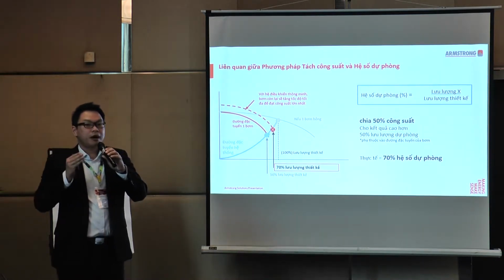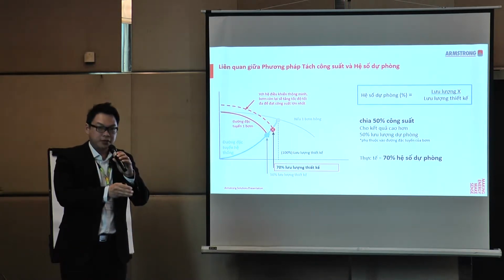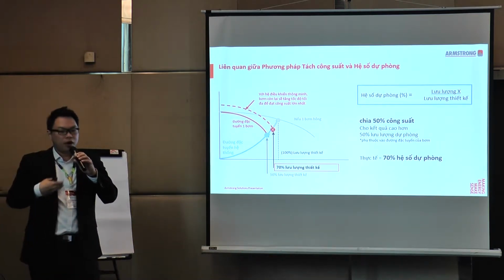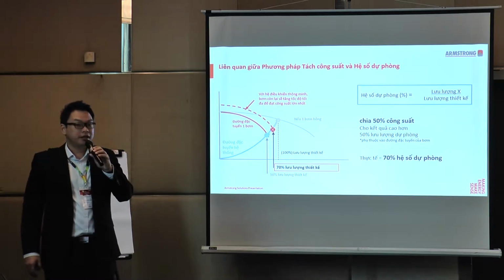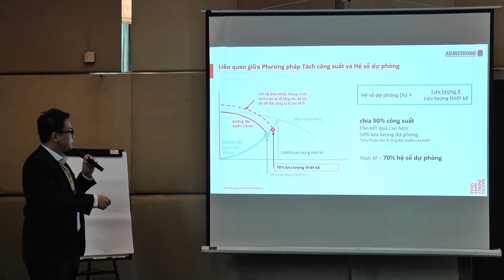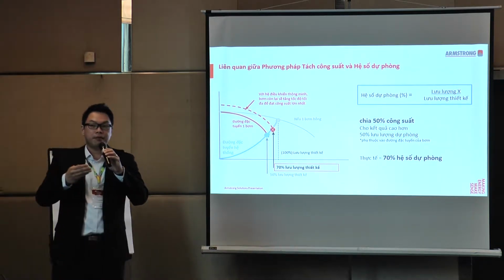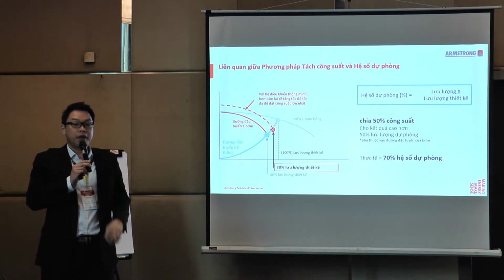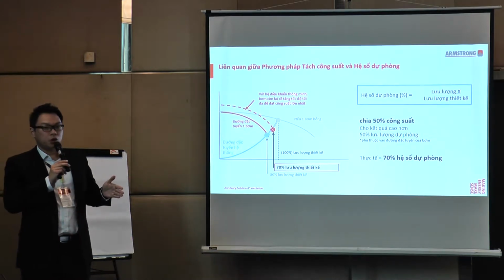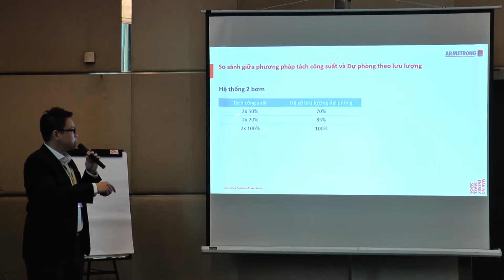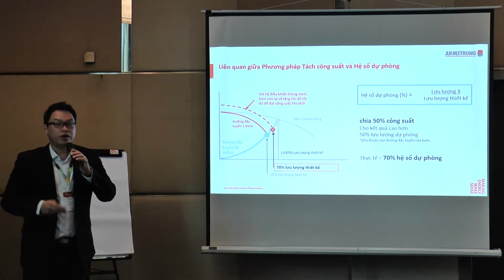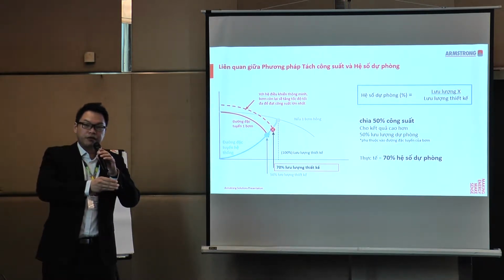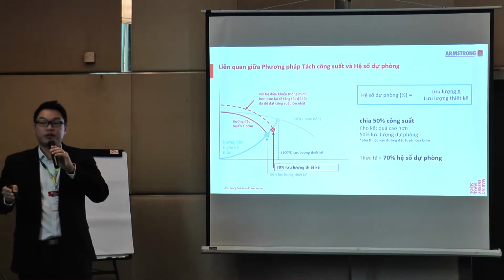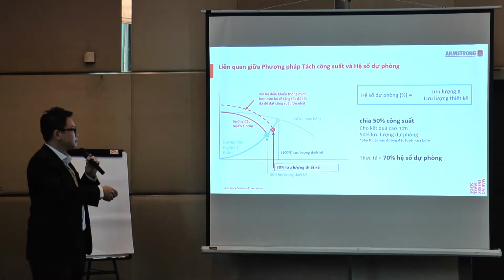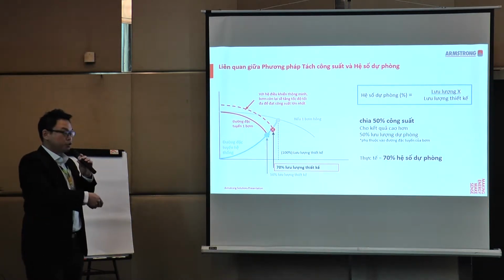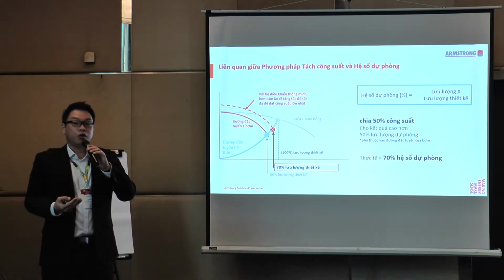Okay. Now, I've talked about redundancy and I've also introduced capacity split. So maybe the next question you might have is, what is the effect of capacity split on redundancy or backup? If you follow the gray line here, that is the combined pump operating curve when two pumps are in parallel. Should one of them fail, we are going to operate on the single pump curve, the red curve. And you realize that even though it's operating on a single pump curve, it still intersects the system resistance curve. At this intersection, if you drop down, based on this graph, it's only able to deliver 70% of the load requirement.